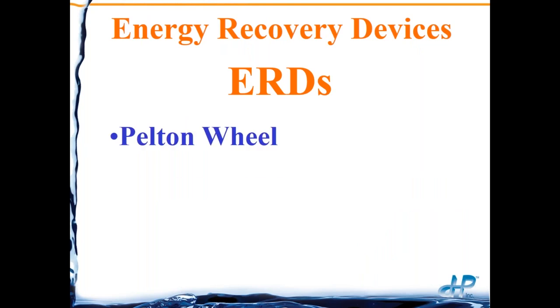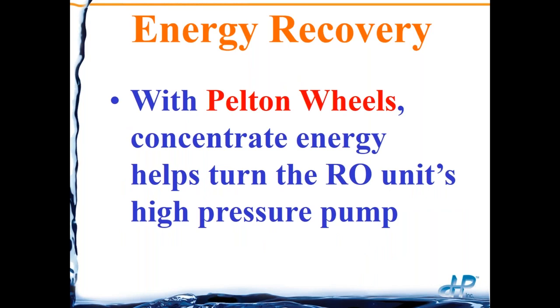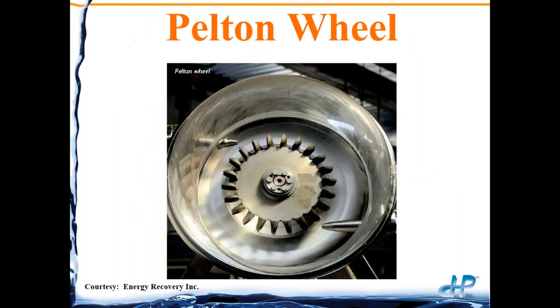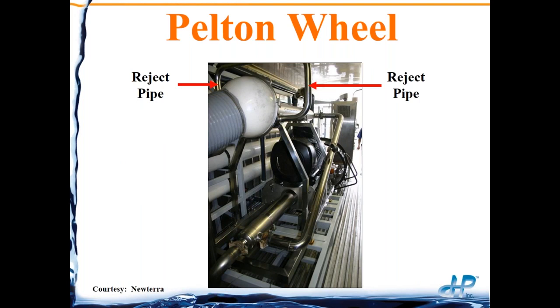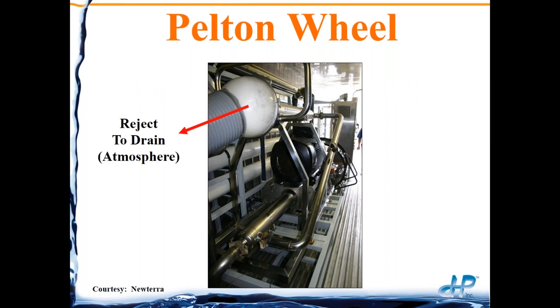There are three general categories: the Pelton wheel, the turbocharger, and positive displacement. With the Pelton wheel, the concentrate energy actually helps turn the RO unit's high pressure pump. Here's a picture — this shaft is coupled to the impeller of the high pressure pump. The reject brine pushes against these fins, which then helps turn the high pressure pump. Here's a small example with a clear housing where we can see the brine exiting. The reject goes against the fins, turns the shaft, and then goes to drain at atmospheric pressure.